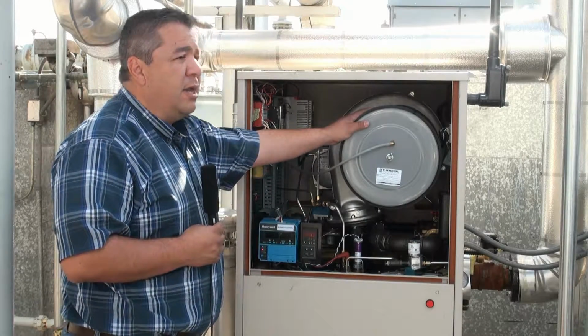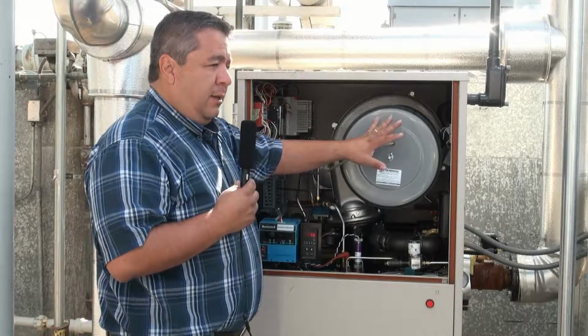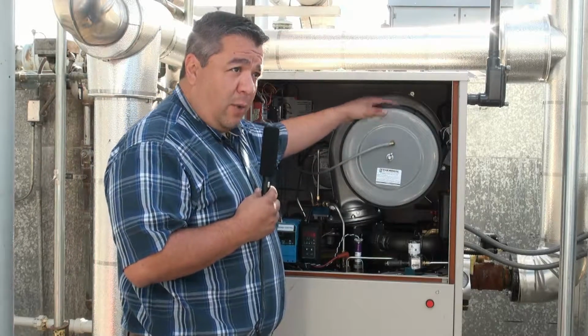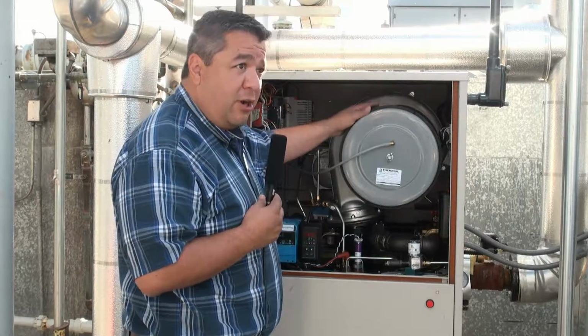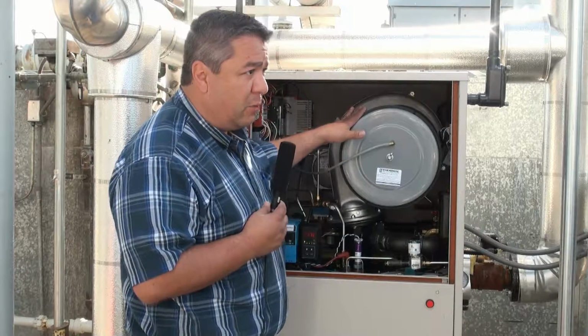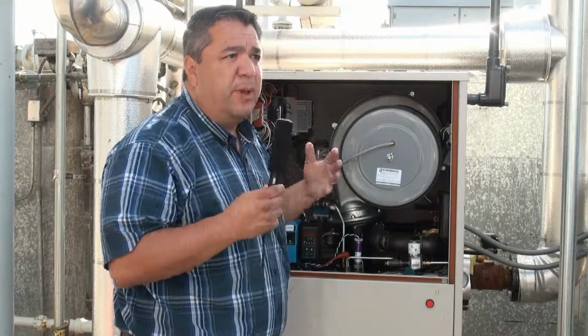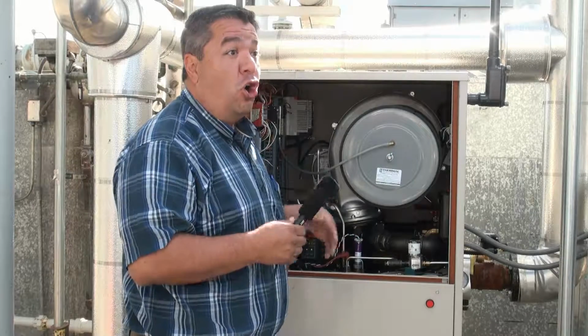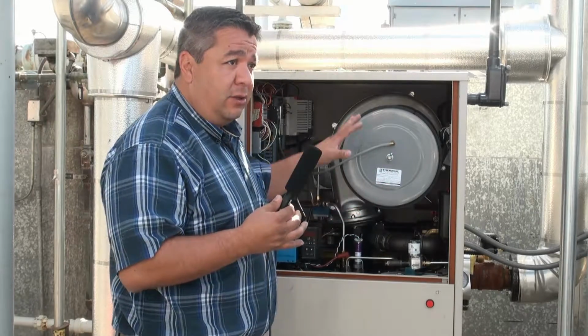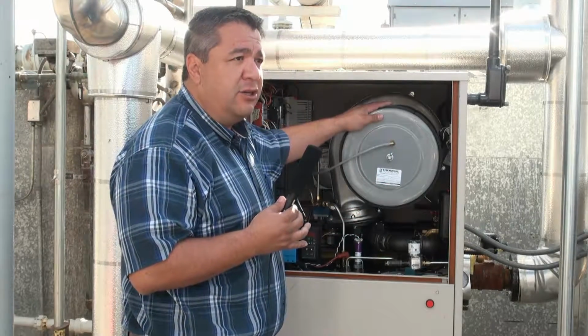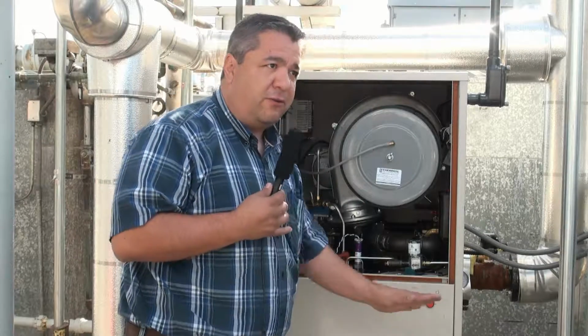You'll hear it going. Now remember, this is just a filter. If you want to test, if you want to see what's going on, take the filter off - don't put your hand in it - but you can see the wheel turning on the fan just to make sure it's spinning in the right direction, everything is good. This filter doesn't have to be in place for the boiler to go into full operation.